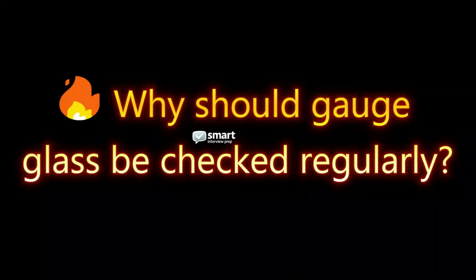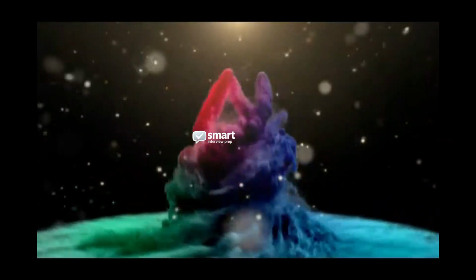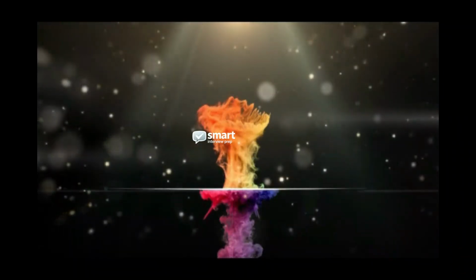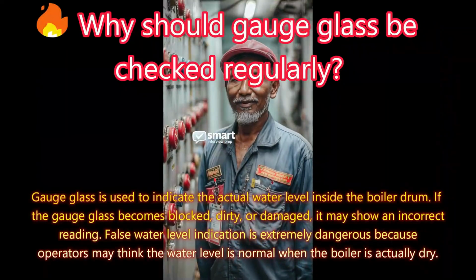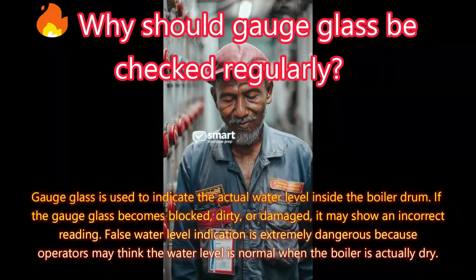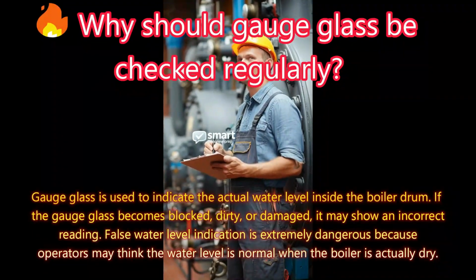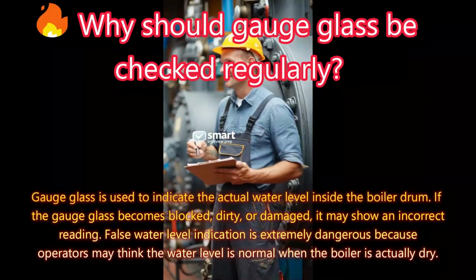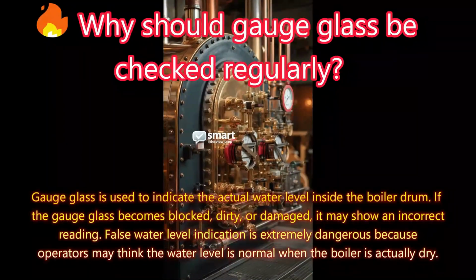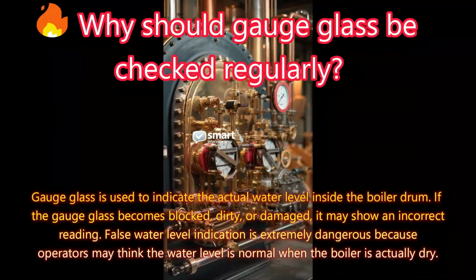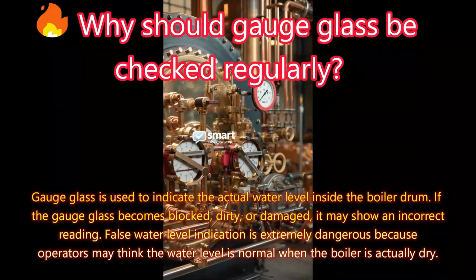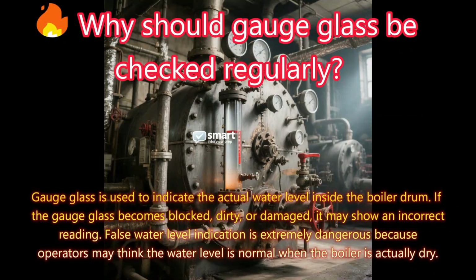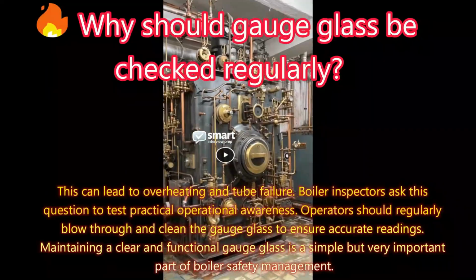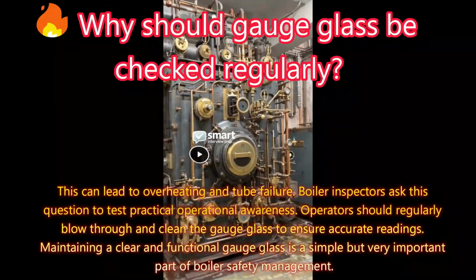Why should gauge glass be checked regularly? Answer: gauge glass is used to indicate the actual water level inside the boiler drum. If the gauge glass becomes blocked, dirty, or damaged, it may show an incorrect reading. False water level indication is extremely dangerous because operators may think the water level is normal when the boiler is actually dry. This can lead to overheating and tube failure.